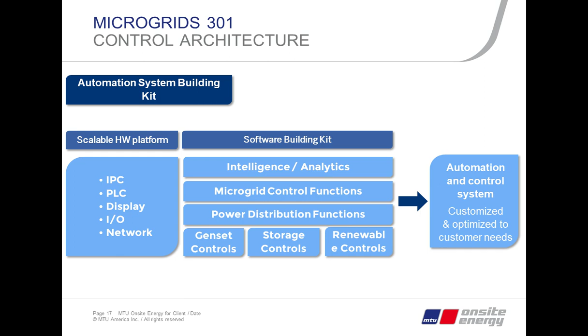Let's talk more about the operational modes we might see in a microgrid. We may have a grid parallel operational mode where we're tied to the grid. In that case, the most basic function of this controller is active power control. We'll set a power set point to import or export power to the grid, or neither, basically zero load control. We'll also control reactive power, the KVAR, in much the same way.